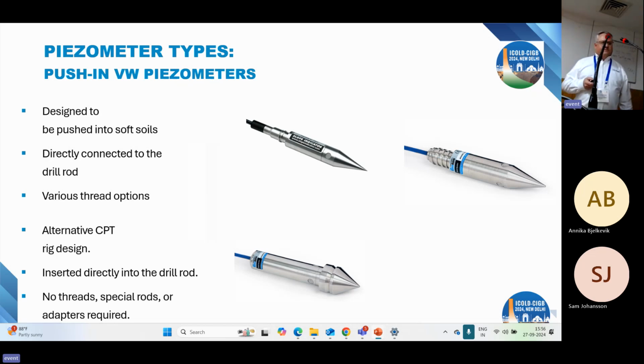There are push-in type piezometers. These are designed to be used with a drill, but it is more of an in situ installation. You typically drill down several feet or meters, and then push it in, say, 1.5 meters or so. You can just drill down to about 1.5 meters above where you want to put it. You push it in, and they have a left-handed thread so you can spin off the drill rod and leave the instrument in place in the ground.